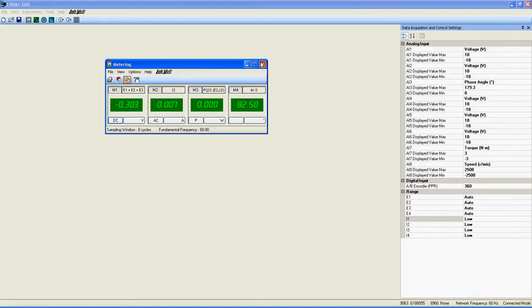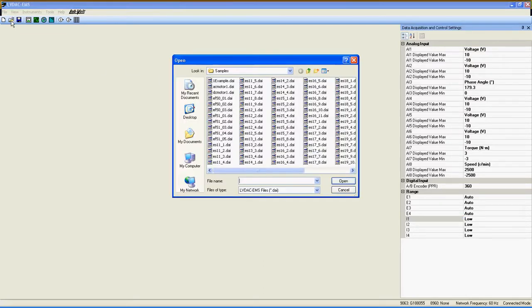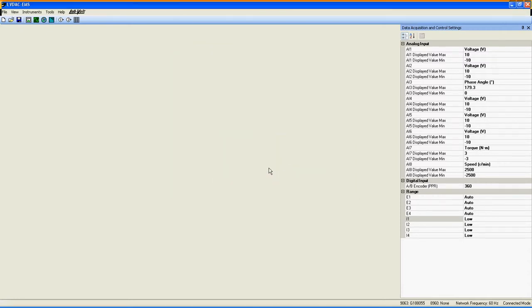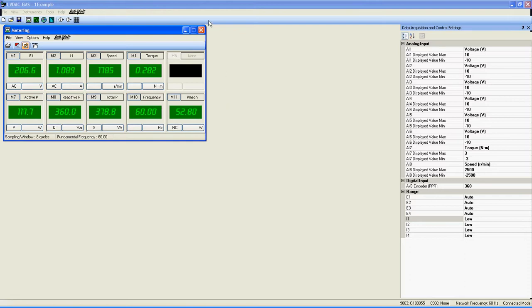I've already connected an induction motor to a power supply, and connected some inputs of the 9063 to this circuit to give you a general idea of what can be easily achieved with this function. I open my saved settings by clicking on File, then on Open. Once loaded, I select continuous refresh of the meter's data. As you can see, I get in real time the input voltage, input current, speed, torque, active power, reactive power, total power, frequency of the input voltage, and mechanical power of the induction motor. Every important parameter relative to this motor is easily displayed and can be read here in seconds. Combined with the data table, which is able to record every meter found in the metering window, you get a powerful tool when it comes to data acquisition. This concludes the tutorial about the metering window.